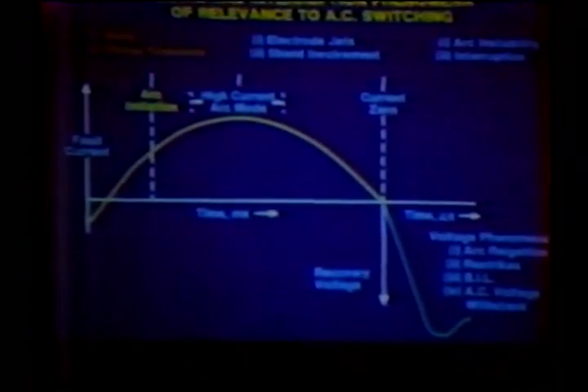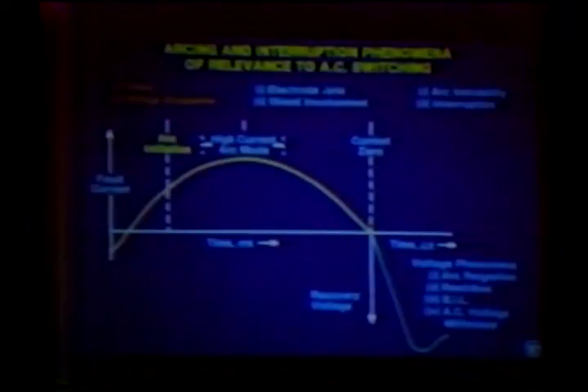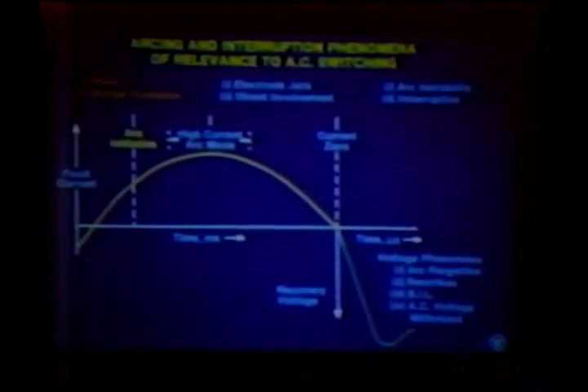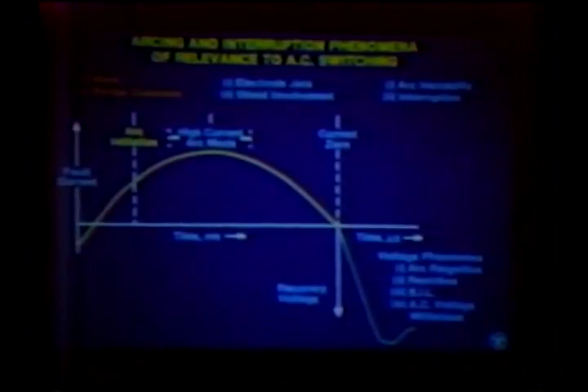At this time I would like to imagine that the fault has occurred, that this is the fault current wave, that we interrupt at current zero, and this is the recovery voltage wave. Going step by step, assuming that we've separated the contacts during the rise of that wave, let's look at the factors involved with arc initiation, with the high current arc mode, with what happens at current zero, and then the types of phenomena involved following current zero when the recovery voltage is applied across the separated contacts.